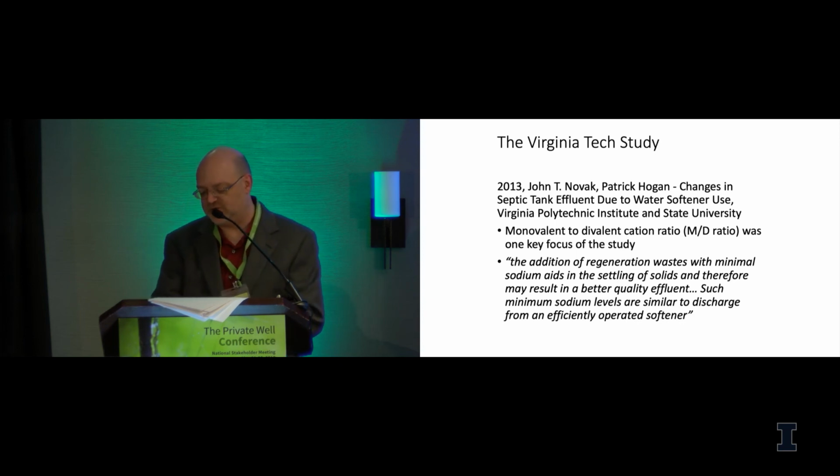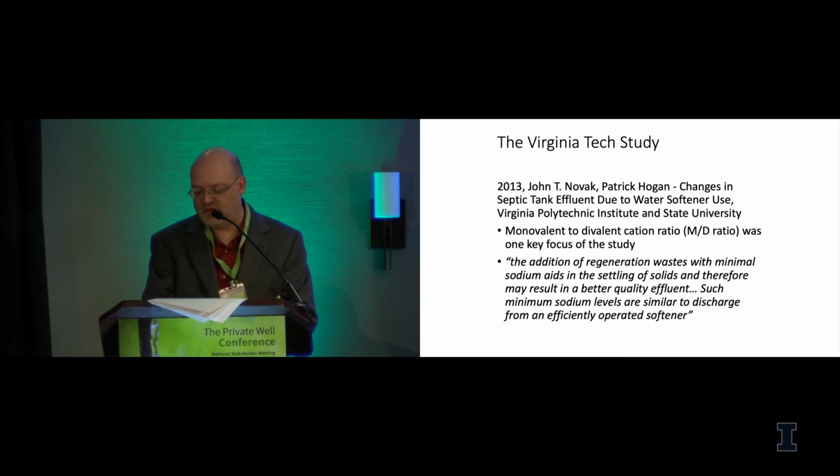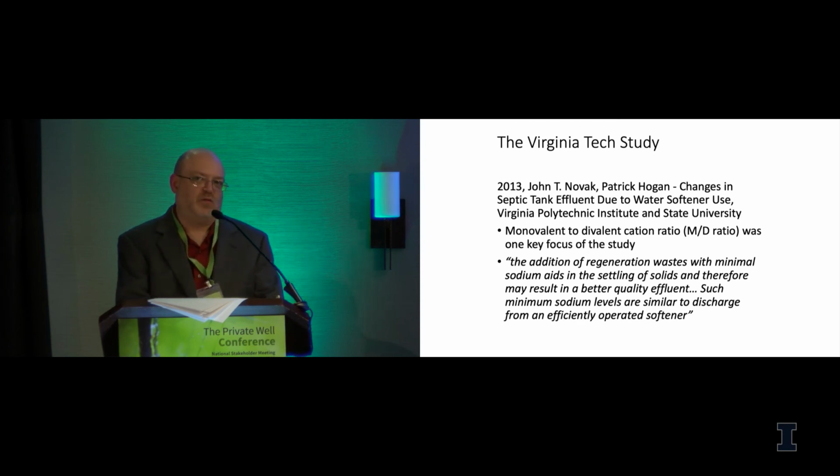Their finding from this study was the addition of regeneration waste with minimal sodium aids in the settling of solids and therefore may result in a better quality effluent. Such minimum sodium levels are similar to discharge from an efficiently operated softener. So we did again have this finding of, okay, there's a beneficial impact, but now at least we had some science to explain the mechanism.